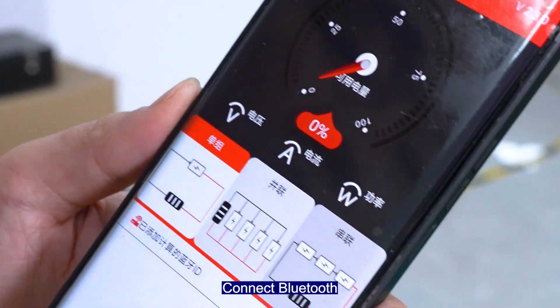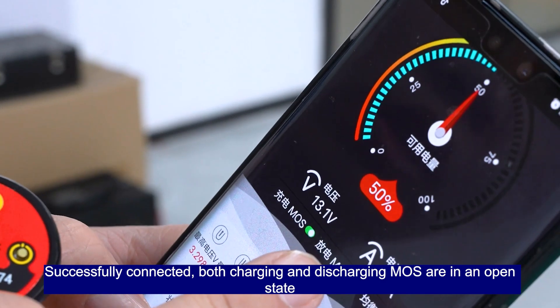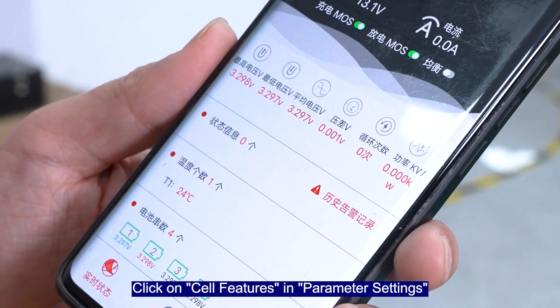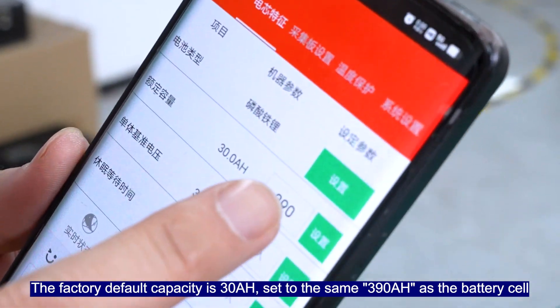Connect Bluetooth. Successfully connected — both charging and discharging MOS are in an open state. Click on cell features in parameter settings. The default capacity is 30 ampere-hours; set it to match the battery cell at 390 ampere-hours.